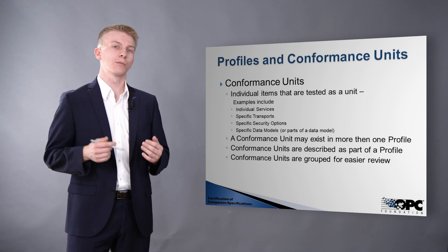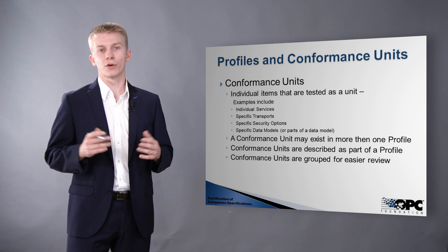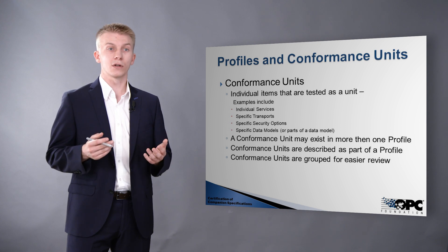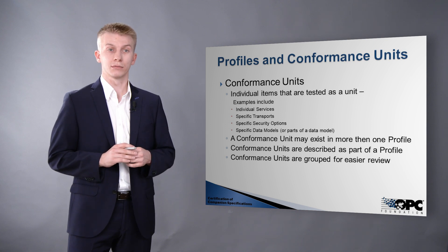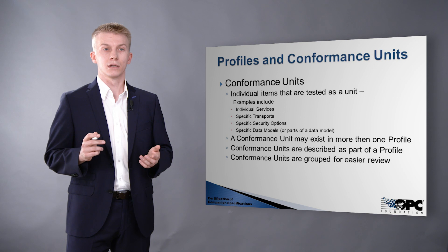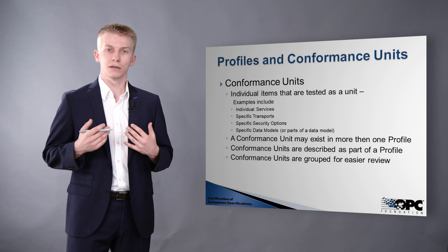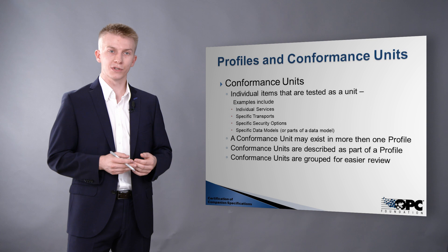A conformance unit is the smallest testable unit. That can be, for example, individual services, but also specific transports, specific security options, or your data model — even parts of the data model can be a conformance unit. A conformance unit may exist in more than one profile, and conformance units can be optional or mandatory. The same conformance unit can be optional in one profile and mandatory in another. Conformance units are described as part of the profile, they have test cases related to them, and they are grouped in conformance groups for easier review.